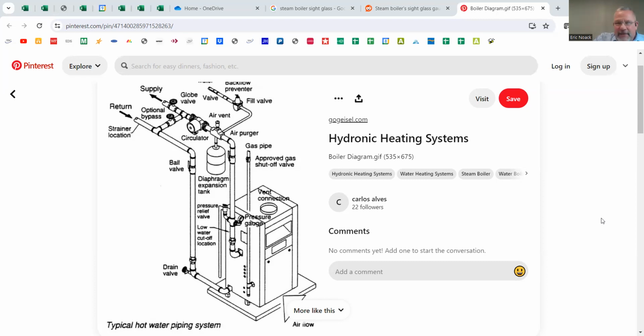On a boiler, it's not temperature controlled. You can get the water as hot as you want, basically. You know, in some boilers, it runs up close to boiling, up into the 200-degree level. But it will release on pressure, and from my memory, they're 30 psi is what they're set at. So if that pressure relief valve is popping off, and you can see that because there'll be evidence of water dripping down on the floor, corrosion, mineral buildup, that kind of thing, oftentimes that means there's a problem in that fill system. Either the diaphragm expansion tank has failed, so it fills it up, and then there's nowhere for it to go when it warms up. It overpressures and it pushes out of that relief valve. There could be multiple reasons, but the diaphragm failure is a common one.